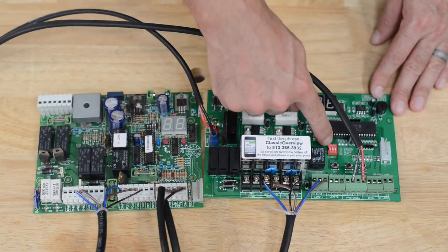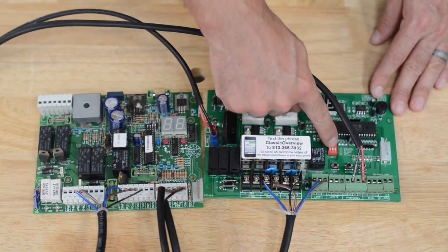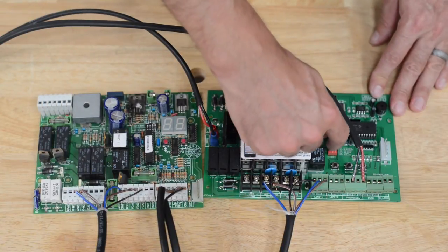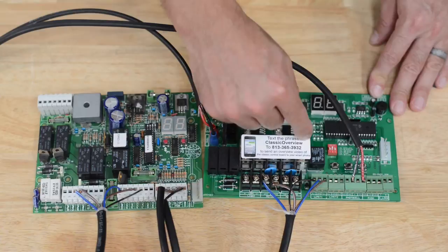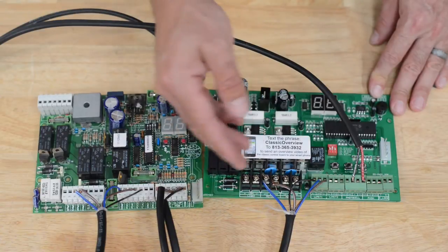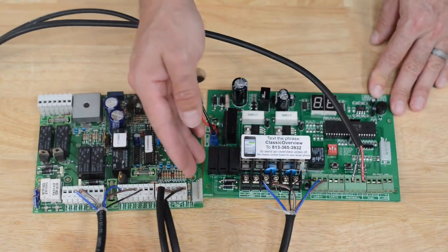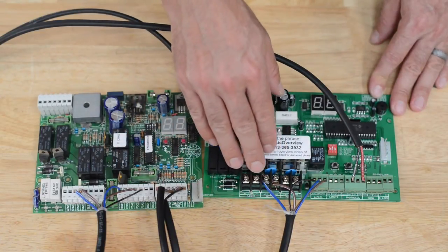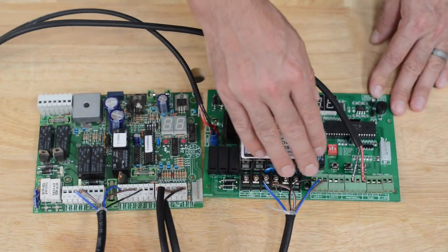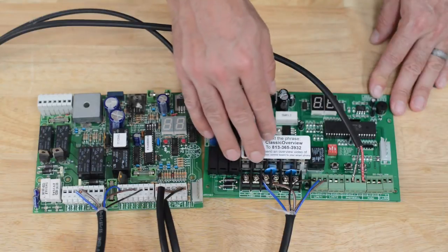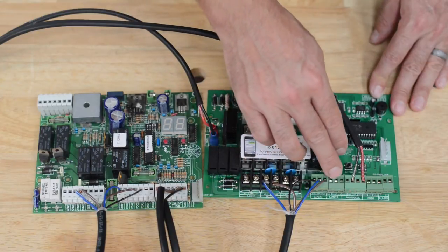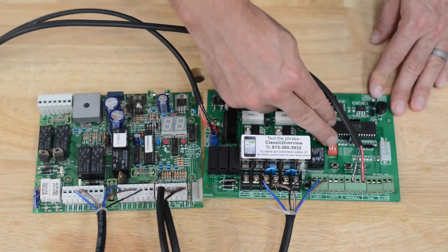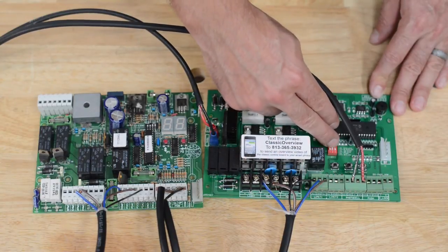For a dual system, the center dip switch number two will remain in the default up position. But again, if you only have a single, you would wire into motor one and limit one, and you would leave motor two and limit two blank and move the second dip switch to off.